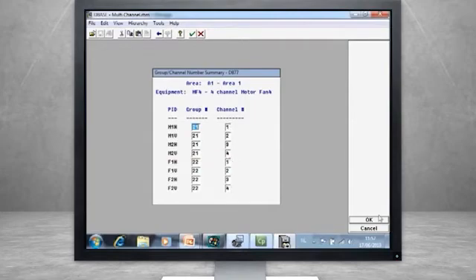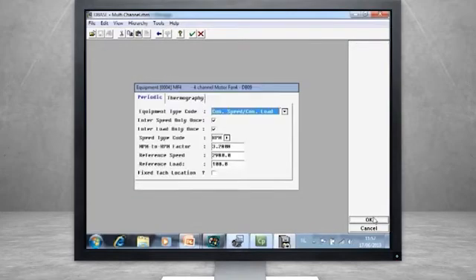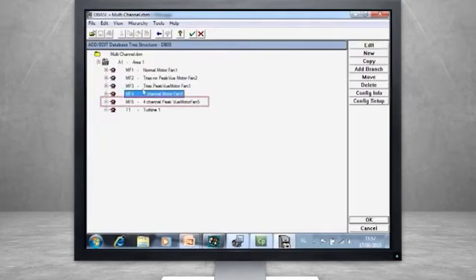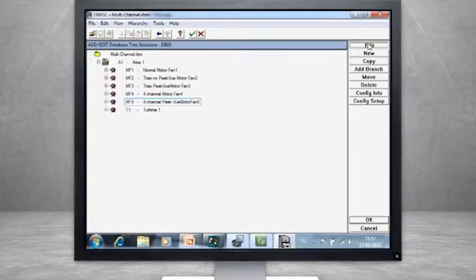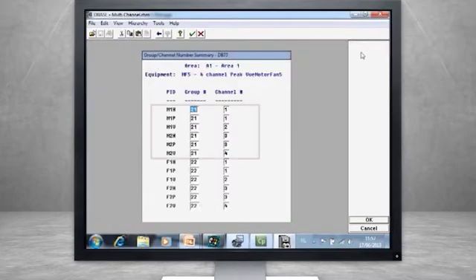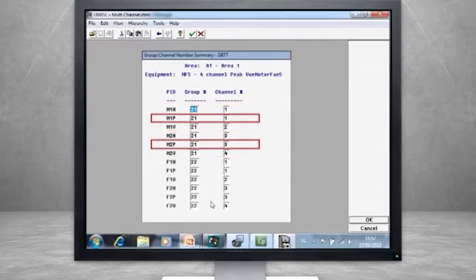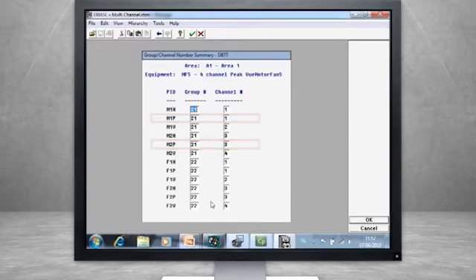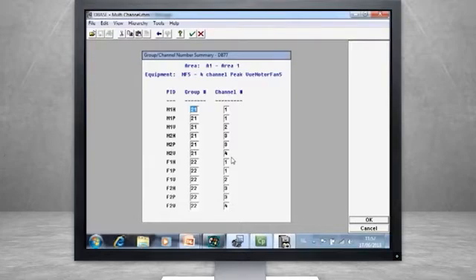If you want to add a peak view measurement to that configuration, it would look something like this. Here we have six points in the same group. Four of the six points will be collected simultaneously, and the two additional points will be collected automatically in sequence. Even though you are limited to four channels simultaneously, you need only start the data collection once to take all six points, giving the illusion of six simultaneous points.